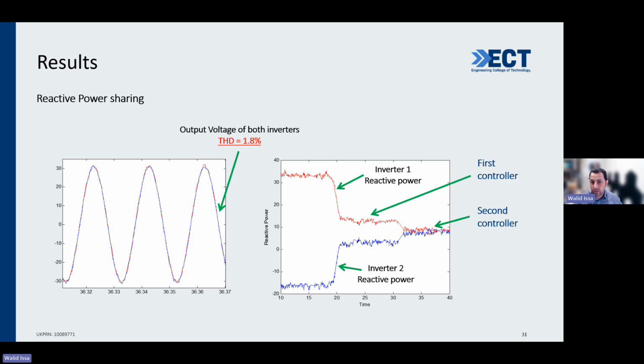When injecting into the grid, or with two inverters that need to integrate with each other, here's what happens: the reactive power of inverter 1 and inverter 2 are not similar, and we have to make them similar because we want exact reactive power sharing. So I developed a controller. This is before enabling the controller, and this is after - we achieved equal power sharing between them.